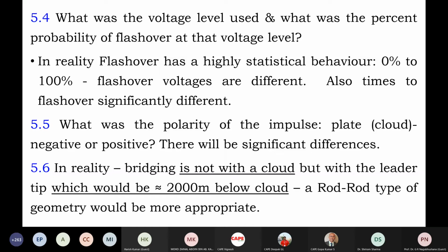Now, next, what was the voltage level used in these experiments? What was the percent probability of flashover at that voltage level? I'm sure every high voltage engineer knows that the flashover probability of a gap depends upon the voltage. For example, at a certain voltage, there may be no flashovers even if we apply 10 impulses. This is a typical number that we use in laboratories. If I go on increasing, at some level, out of the 10 impulses, only 1 or 2 may flash over. They call that 10% flashover probability. Like this, we can go to the 50% probability level, which we call the critical flashover level. We go on increasing the voltage further, we get the 100% flashover level.